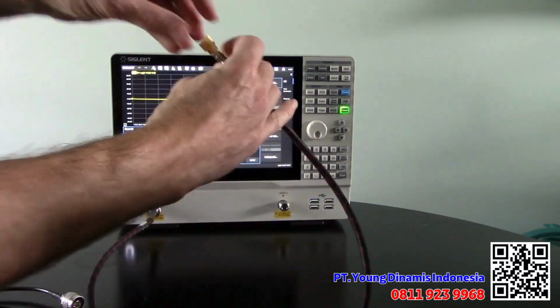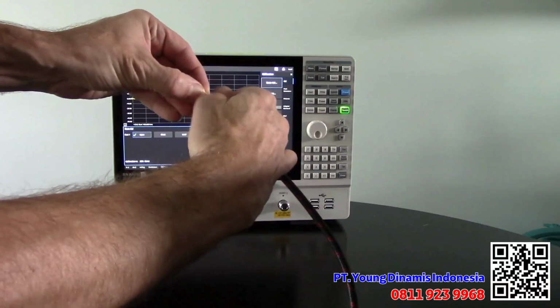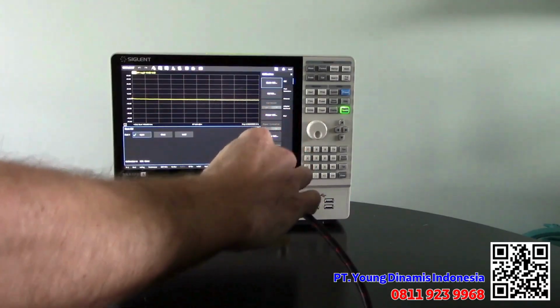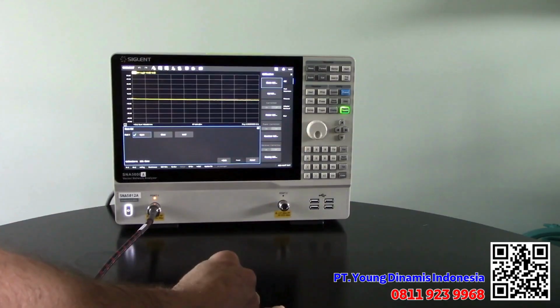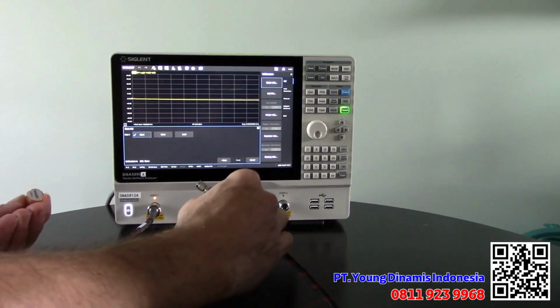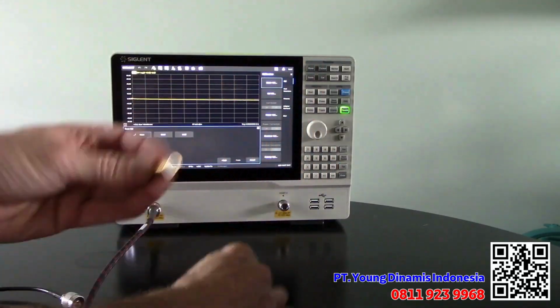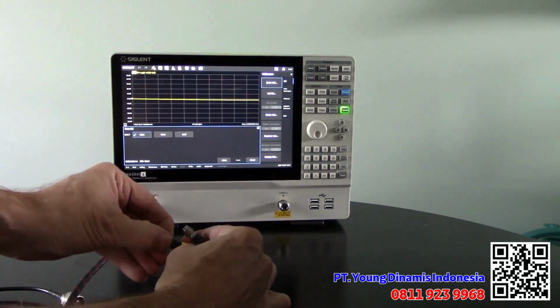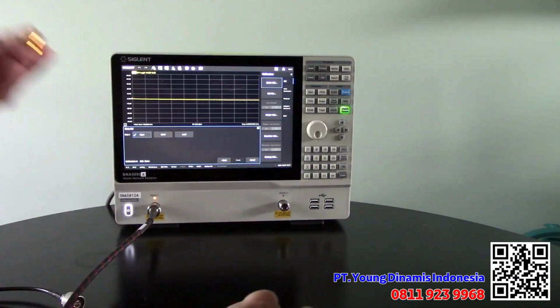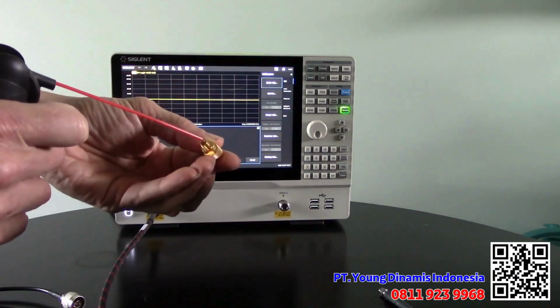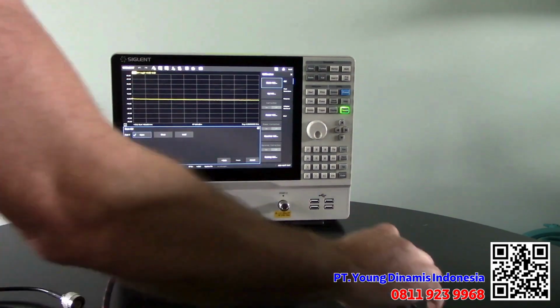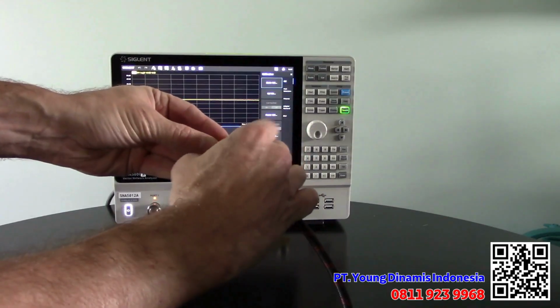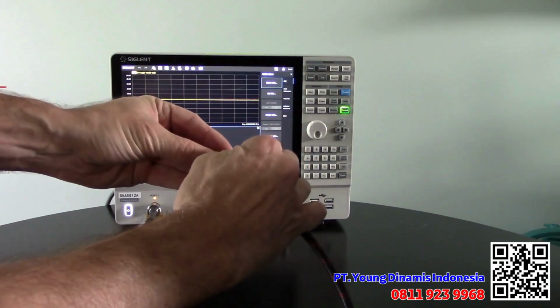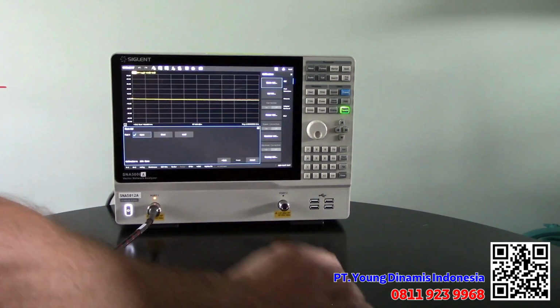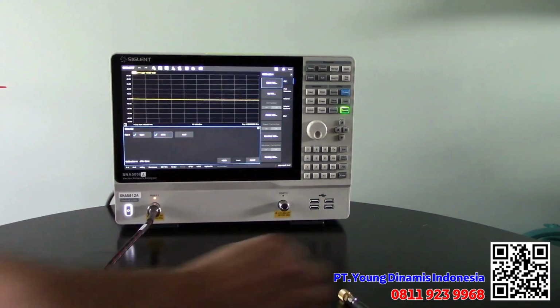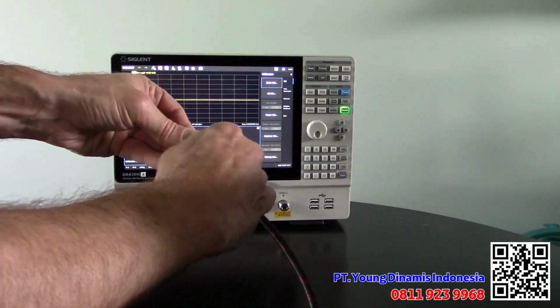We're going to press the open. Once that calibration is complete, we will unscrew the barrel, remove the calibration element, and we're going to move to the short. And so we'll get that element. Here we are with the short, and we're going to then pull its cap off and give it a quick shot with our compressed air. And we will then connect on, again spinning the barrel and tightening, and we're going to then press that button, and we're going to then have that calibration saved.